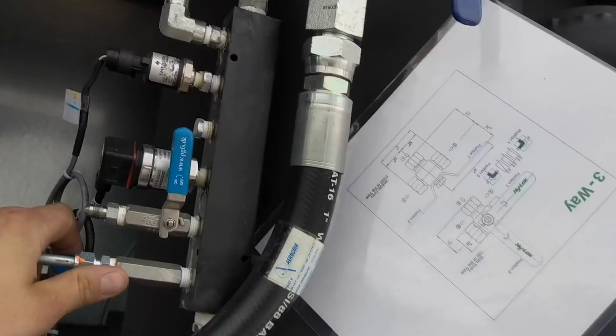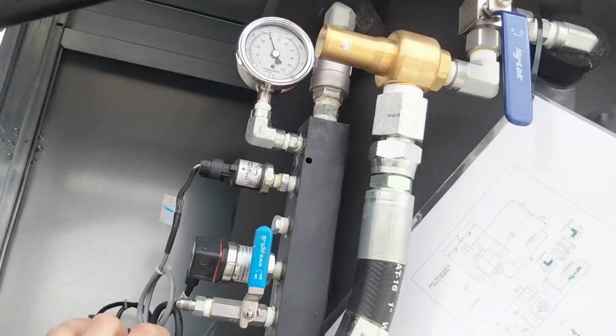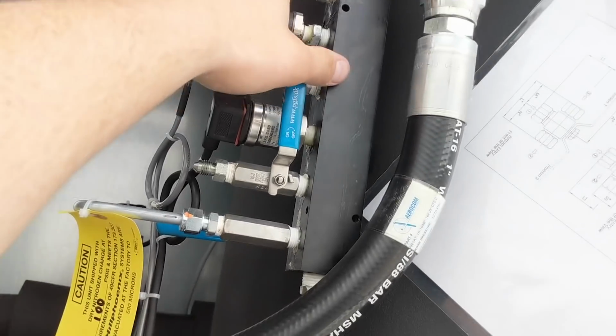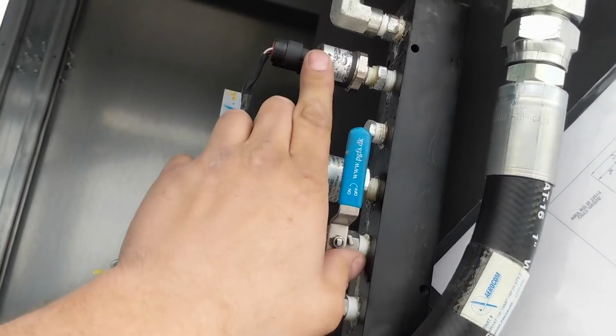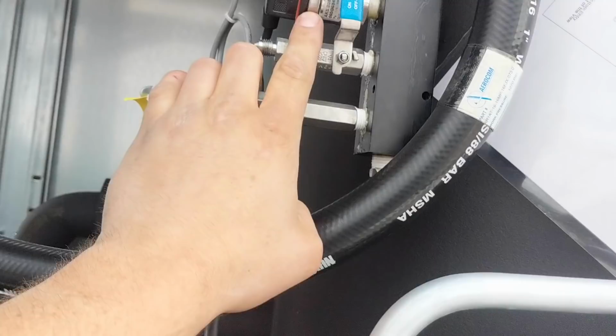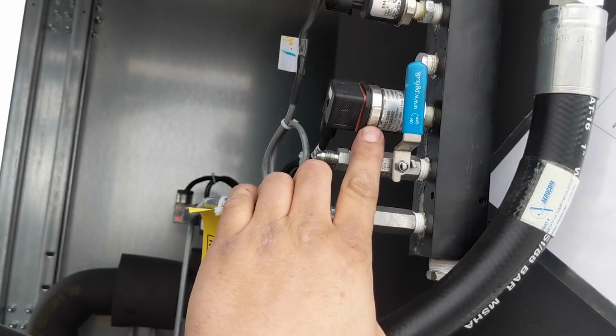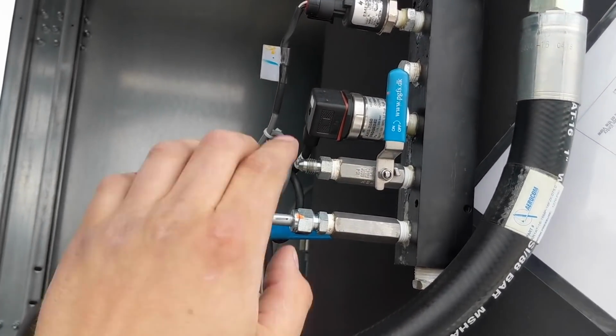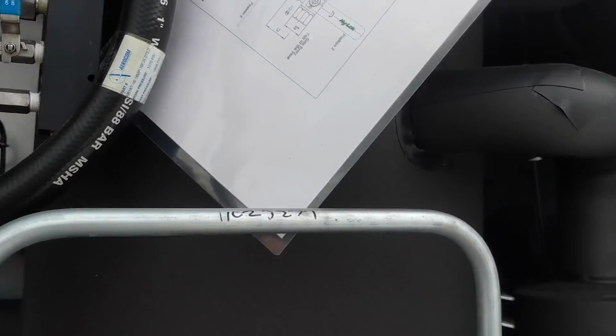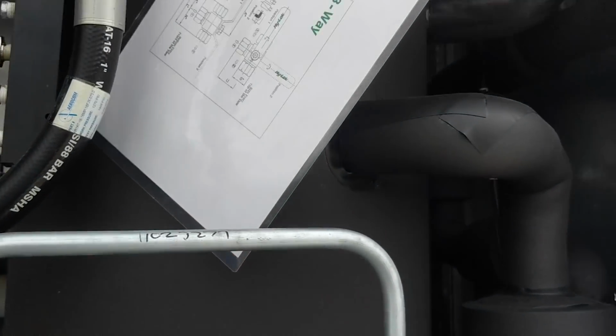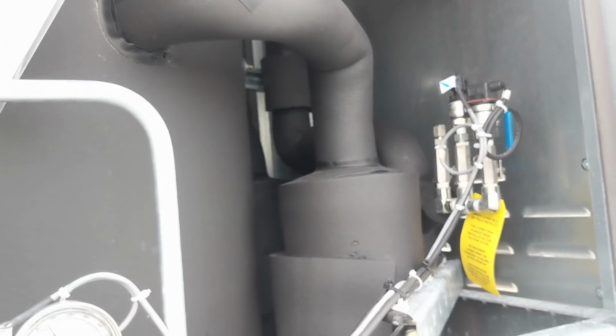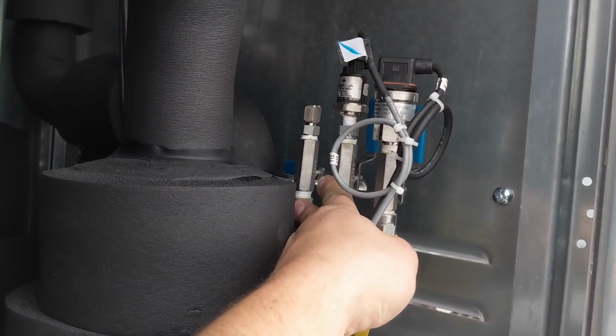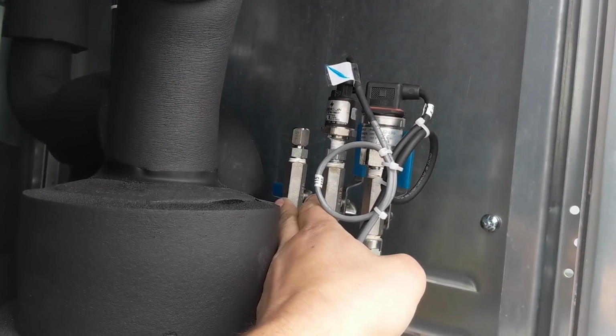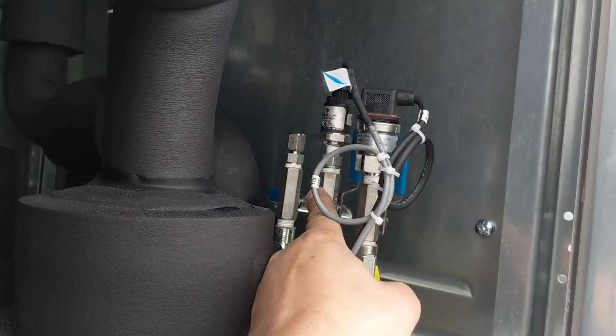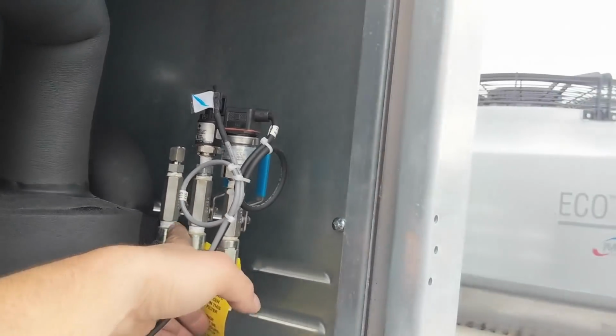Then right here we have our main block for our flash tank. We got our pressure gauge. We got our EMS transducer, flash gas bypass, and high pressure regulator transducer, which we'll go over in a second. Our oil line bypass bleed out is on here, so that's what we're using for that. Then we have our liquid, our high side drop leg transducer, EMS drop leg transducer and a service port.